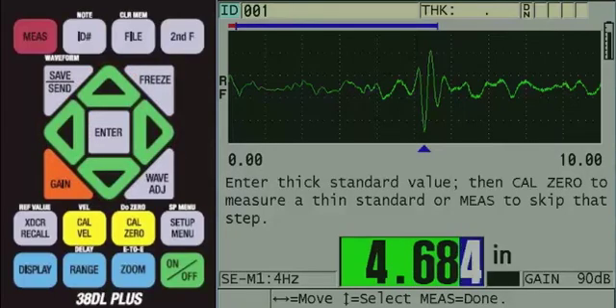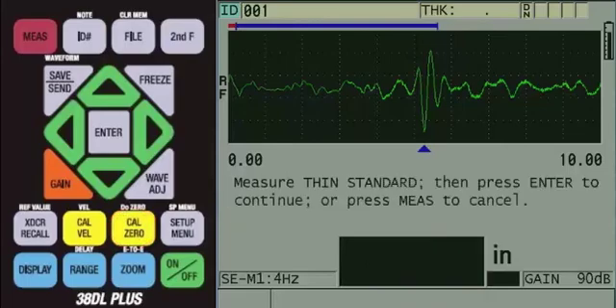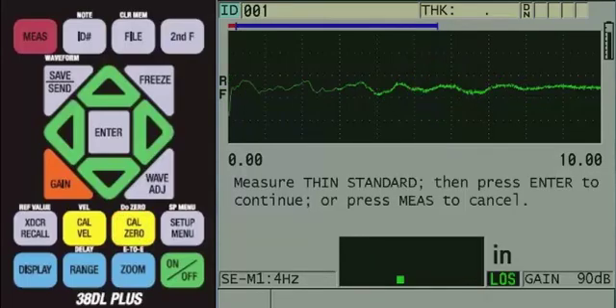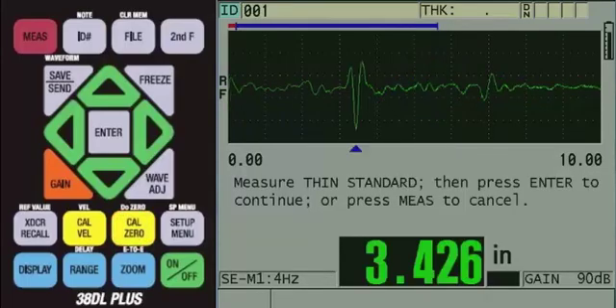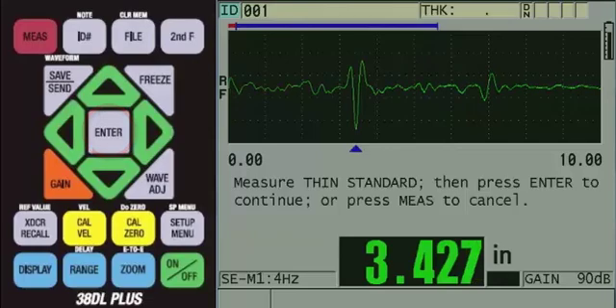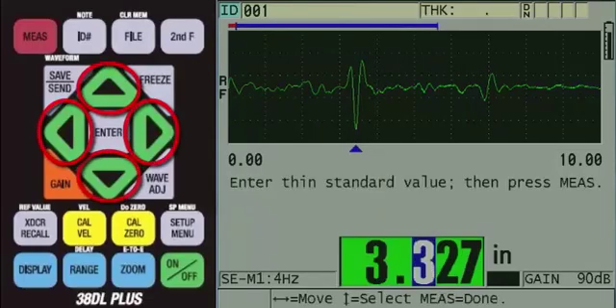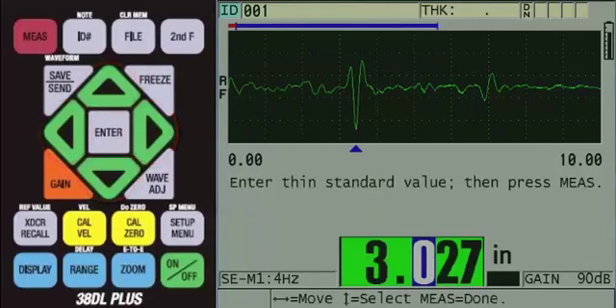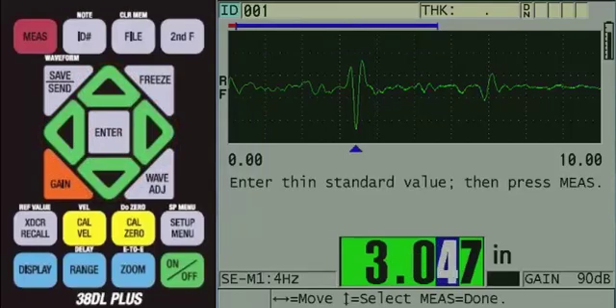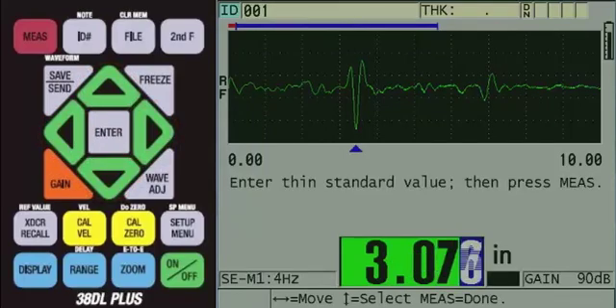Then press the yellow CAL ZERO key and then couple onto the thinnest step. Once you have a steady reading, press the ENTER key. Then use the arrow keys to change the value to 3.071 inches or 78 millimeters, then press the red MEASURE key.